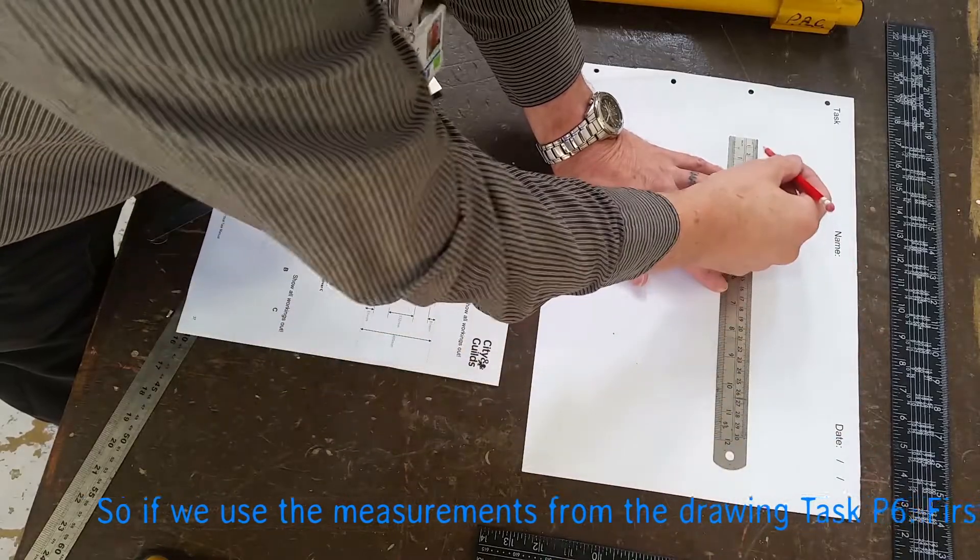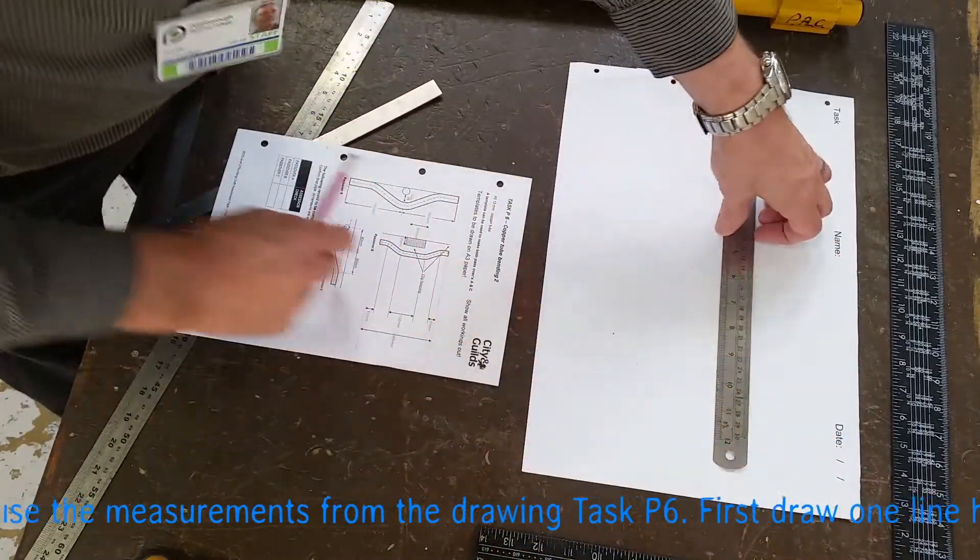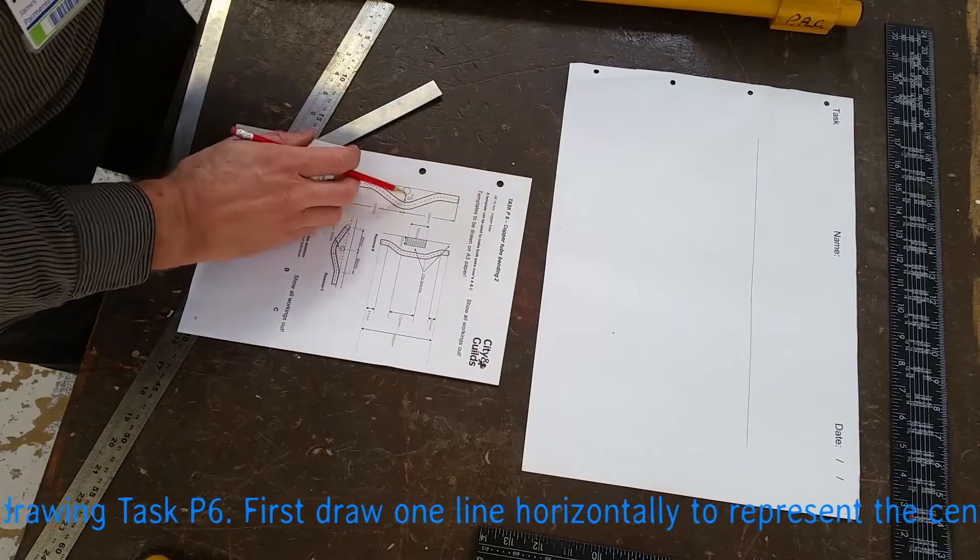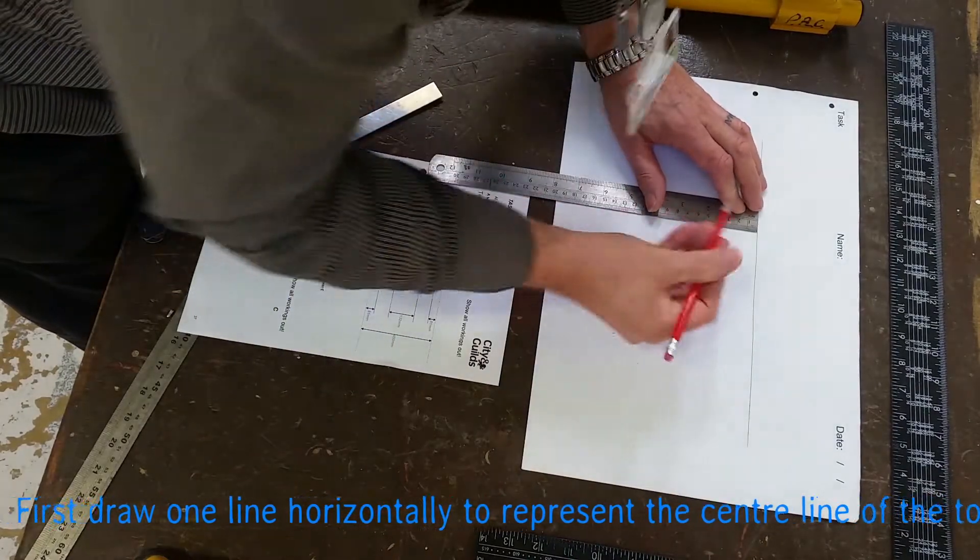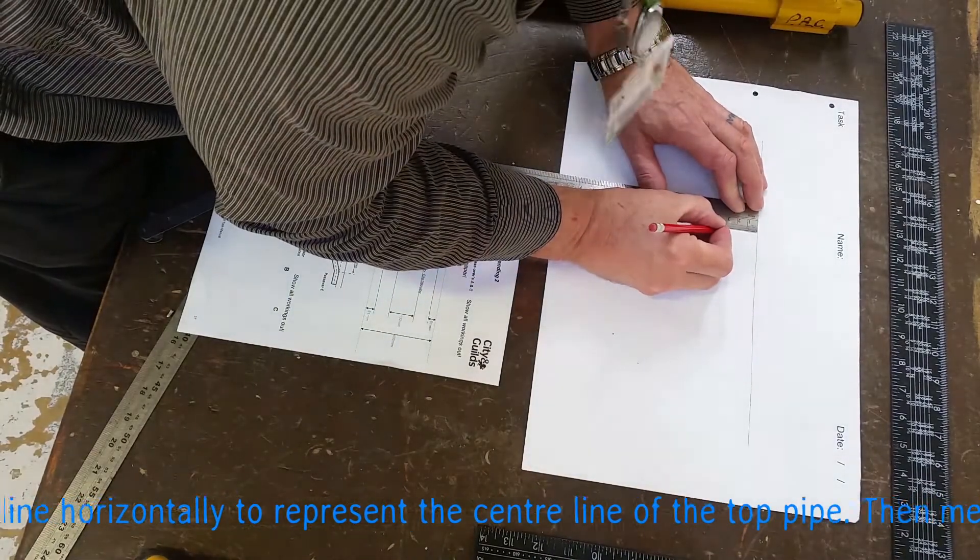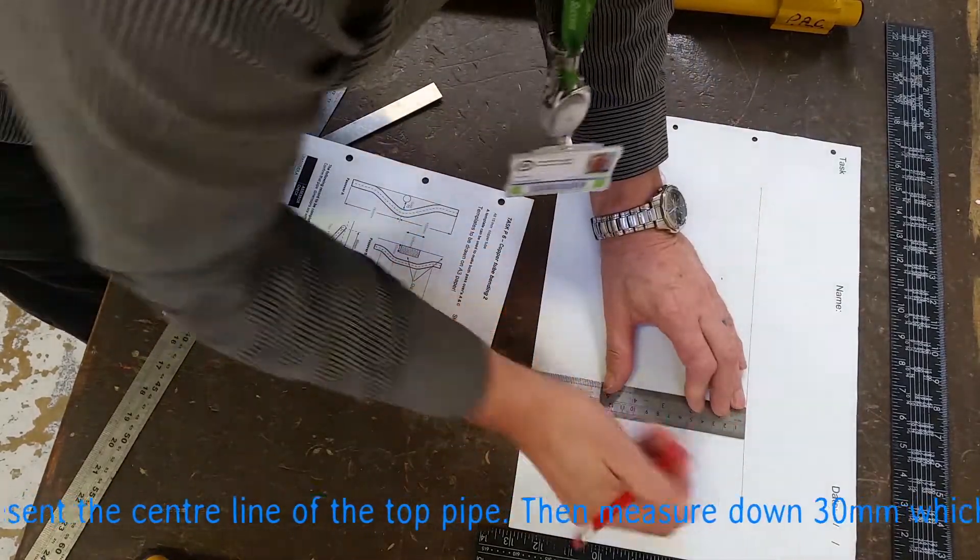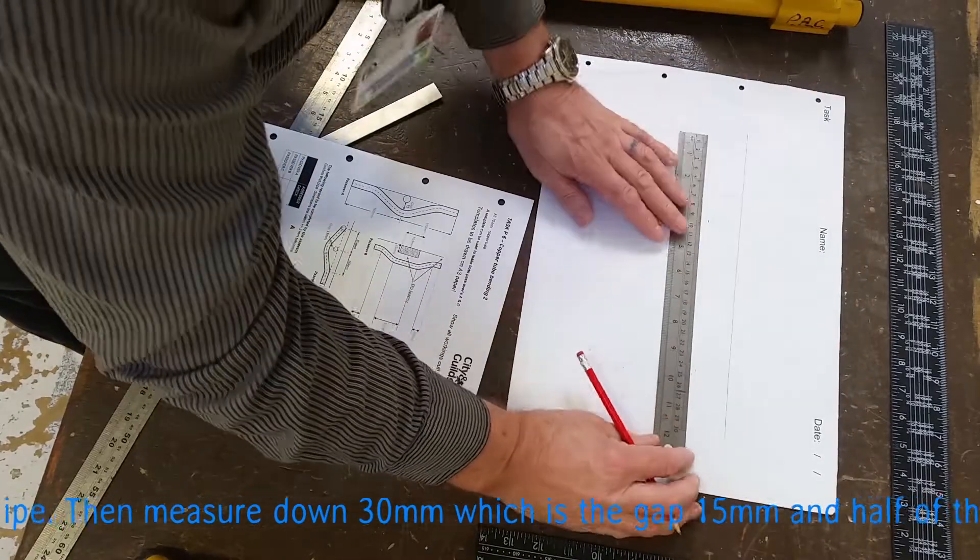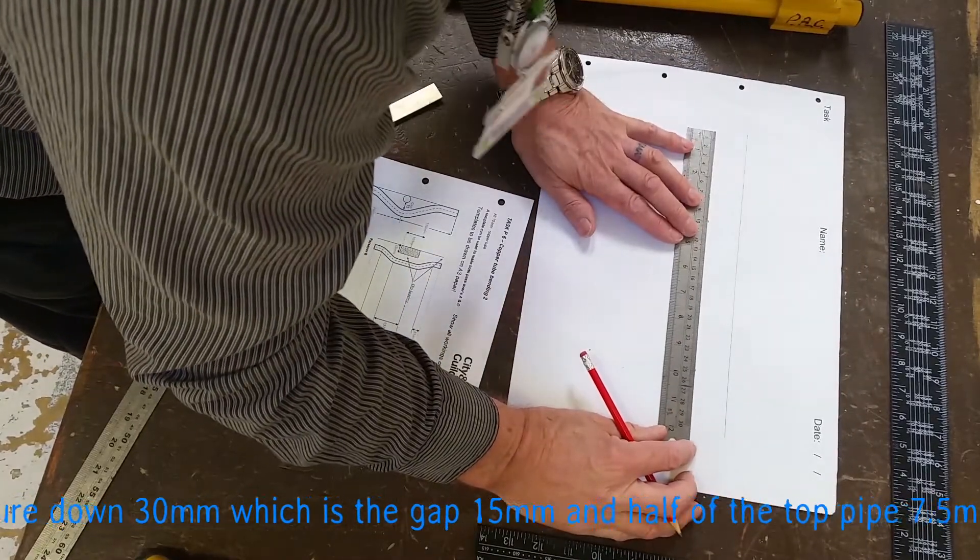Start off by drawing a line which will represent the top bend of our passover bend. Then we've got to measure down 30 because we've got a 15 gap, and we've got half of 15 and half of 15 to get to the center of each pipe. So that adds up to 30. Measure down 30. So we'll end up with two parallel lines 30 apart.